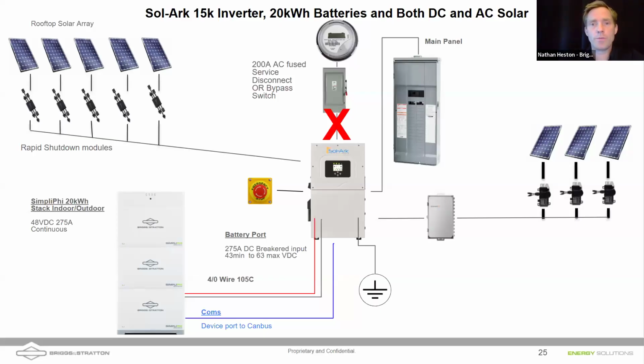So I think the limitation is somewhere around 30 kilowatts of combined AC and DC solar power for these inverters. So in a grid down situation, the AC solar is kept alive. So even though the grid goes down, the batteries can be used. The solar that's there can be used to grid form. So that Sol-Ark inverter in a grid down situation no longer is grid following, it's grid forming. And it can form a grid that the AC coupled solar can latch onto and provide power to. And so you're able to keep both arrays alive in a grid down situation.